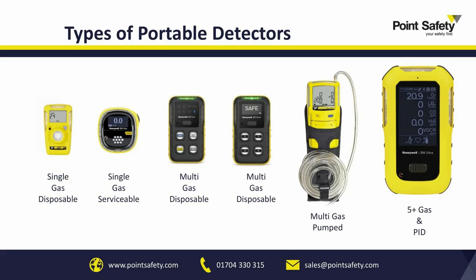You'll then move on to what is your standard multi-gas. It says on here disposable, it should say serviceable. So these have again your primary sensors with the options of additional sensors within there, additional toxics. Some may have the ability to have VOCs in, but most of them are standard 4-gas meters. But you can replace all the relevant sensors. They will require calibration on a maximum of 6 monthly intervals. Again, bump testing is advised on a daily basis if possible.